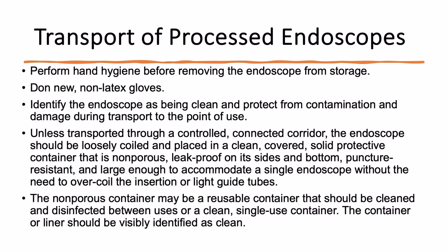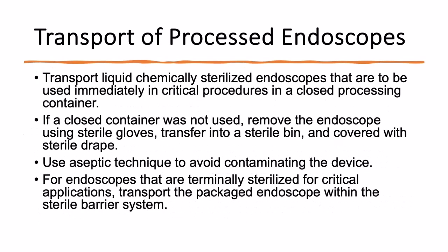placed in a clean, covered, solid protective container that's non-porous, leak-proof on its sides and bottom, puncture-resistant, and large enough to accommodate a single endoscope without the need to overcoil the insertion or light guide tubes. The container can be reusable, and it should be cleaned and disinfected between uses, or a clean single-use container. The container or liner should be visibly identified as clean.